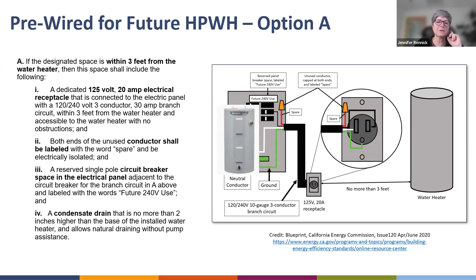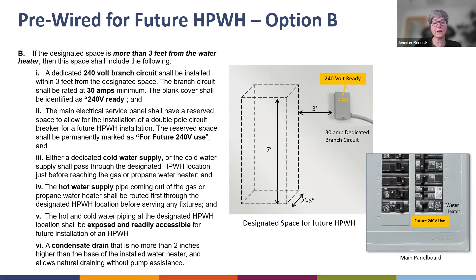So here's a good diagram of what that looks like. Oh, I just noticed I have a floater image there, I'll get rid of that before you get the heat pump water heater, sorry about that. So that diagram will be cleaned up of what it looks like to pre-wire for it, and it also specifically mentions you need that condensate drain because a heat pump does make condensate.